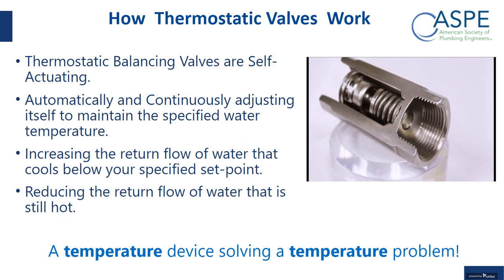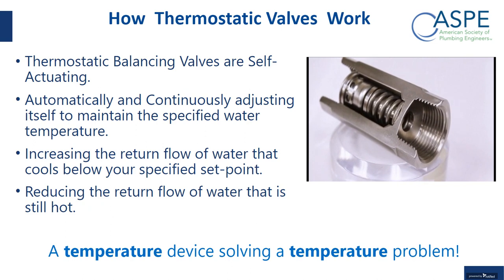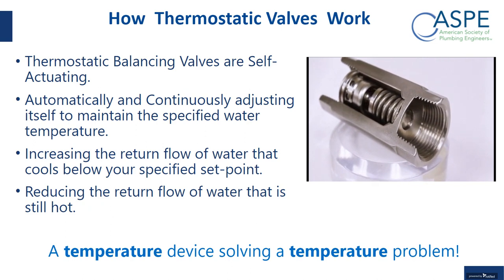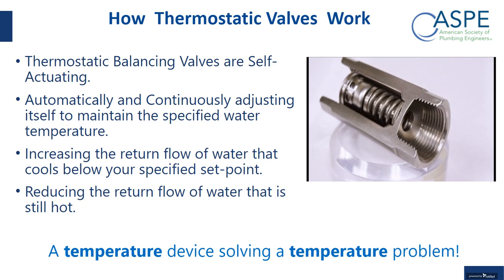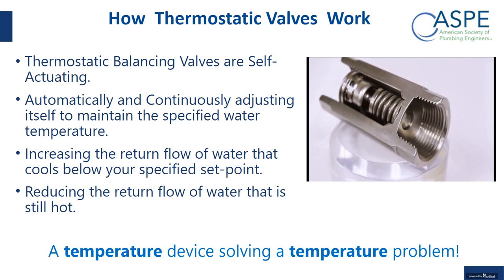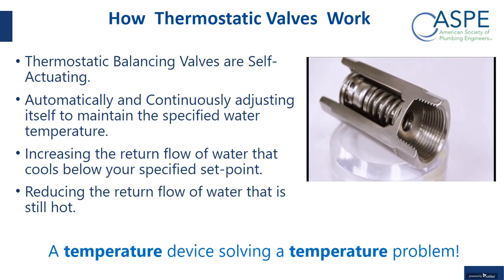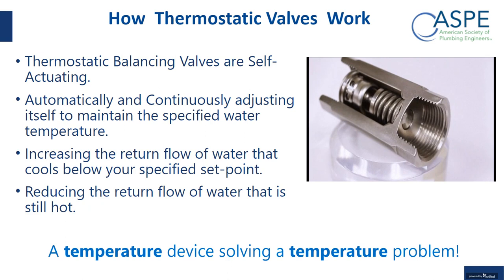So as temperature increases, as I showed in the other slide, the piston extends and it's pushing the plug into that orifice. Now these are designed with a mechanical stop. Regardless of what type of thermostatic balancing valve, whether it's fixed or adjustable, they're designed with a mechanical stop so that the valve never fully closes. That's one of the first questions we get from engineers all the time. They're worried that if you get to the temperature, the valve closes, and then you're deadheading the recirc pump or overheating it.